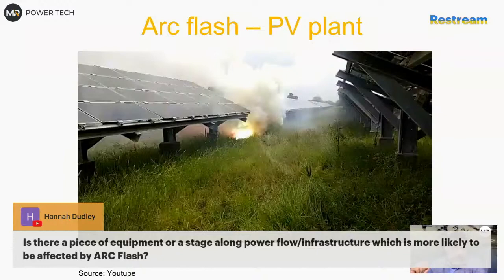Sometimes you have a switchgear where the bus is not on top but on the bottom. Don't ask me why. This one is more likely to have an arc flash because gravity works. If something falls down, it falls directly on the bus bar. When I go on site, I also do a visual check, and because we don't do any risk assessment in the strict sense, I also identify shock hazard issues, which are at the same point arc flash hazard issues. You will see things like exposed equipment. It is very highly likely that something might happen.